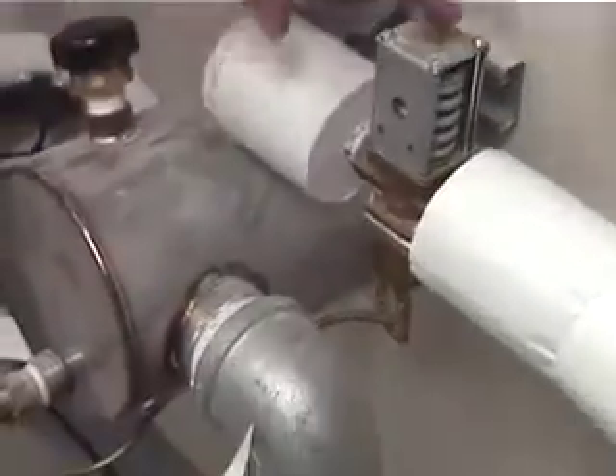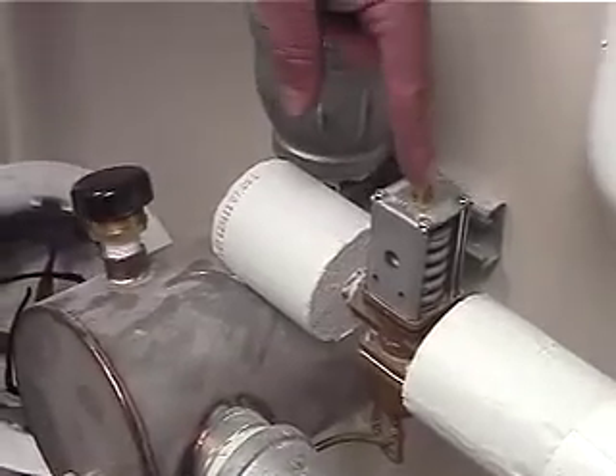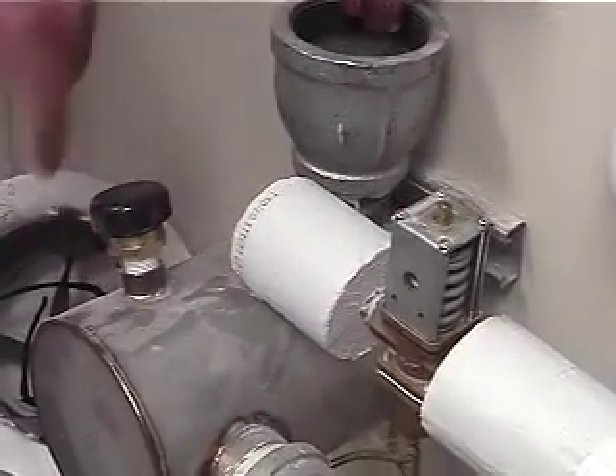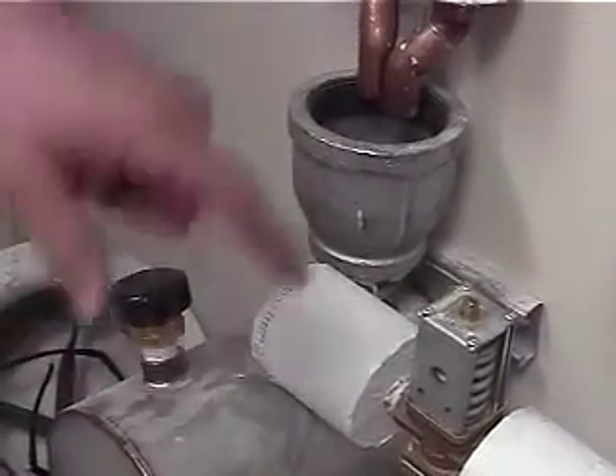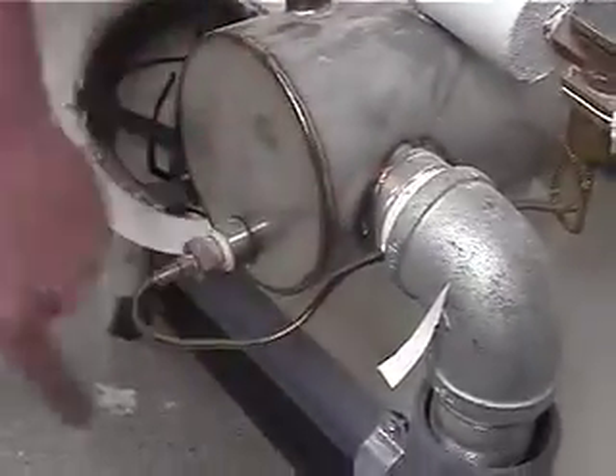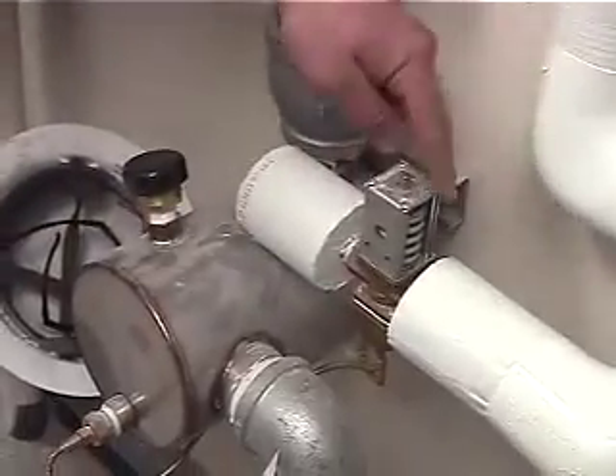So, purpose of drain cooler, fresh water line coming in. Sensor, if you need to adjust this, you do it through this little bolt right here. It's on a temperature. Hot water hits here, it mixes the cold hot water, fills up halfway before it allows it to run over and back down the drain. You want it to be 100-degree water? Adjust the thermometer for 100-degree water. You just got to remember, the lower you get that, it's eventually going to get almost room temperature where it's always going to be running so much cold water all the time. Okay? And that's done right here through this little Penn Johnson valve.